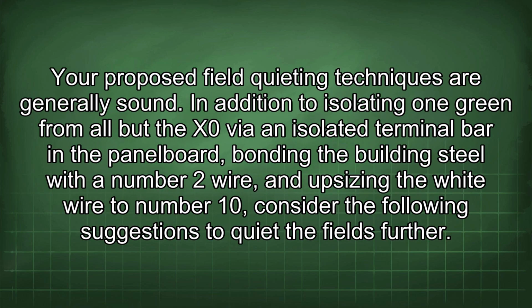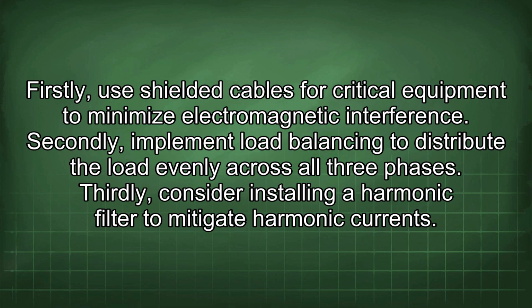Here, the proposed field quieting techniques are generally sound. In addition to isolating one green from all but the X0 via an isolated terminal bar in the panel board, bonding the building steel with a number 2 wire, and upsizing the white wire to number 10, consider the following suggestions to quiet the fields further. Firstly, use shielded cables for critical equipment to minimize electromagnetic interference. Secondly, implement load balancing to distribute the load evenly across all 3 phases. Thirdly, consider installing a harmonic filter to mitigate harmonic currents.